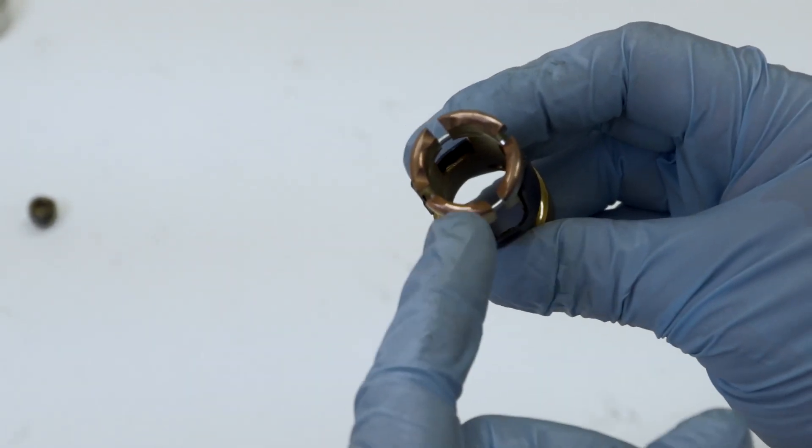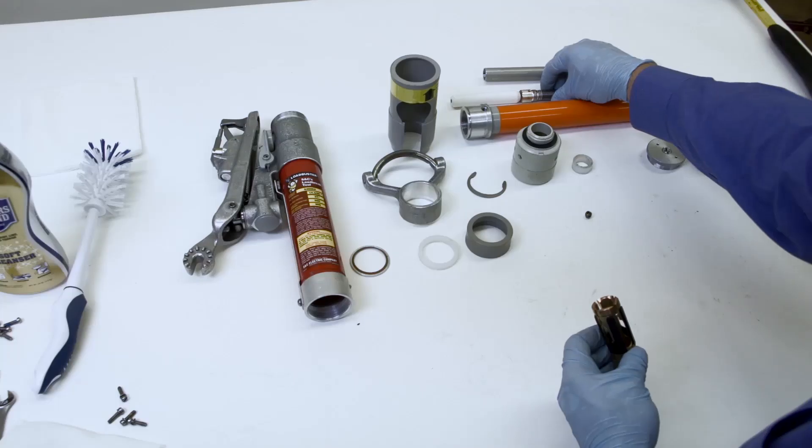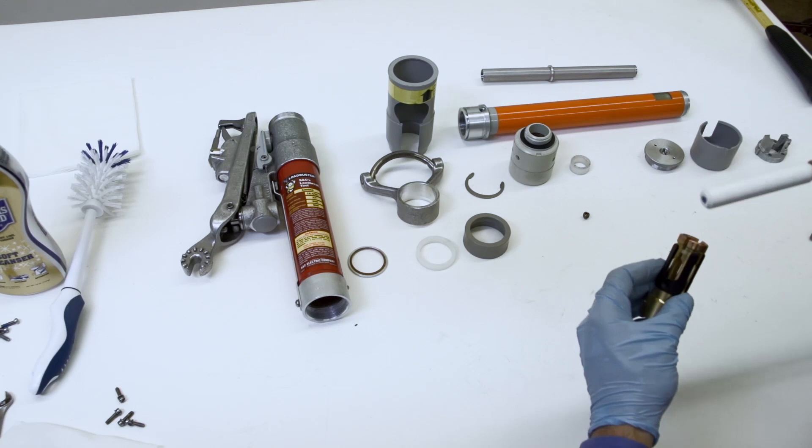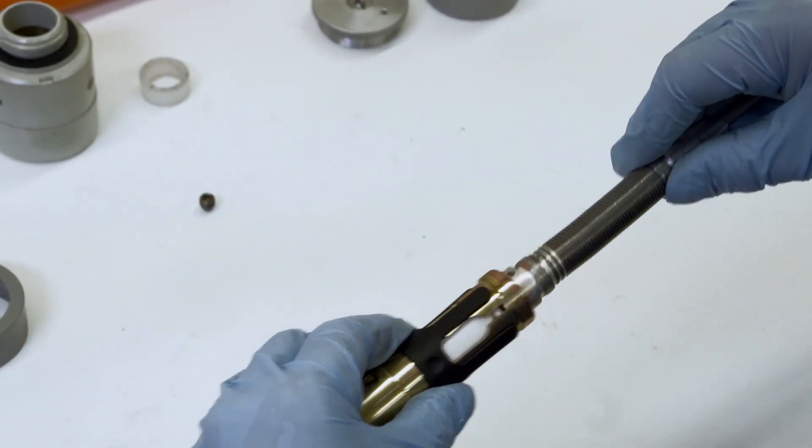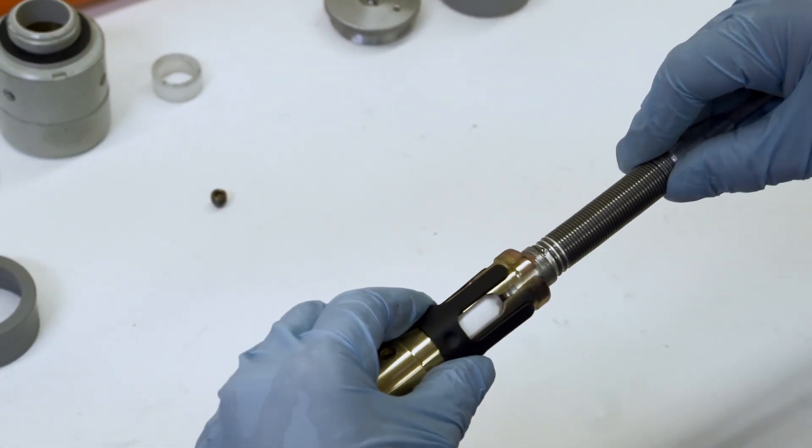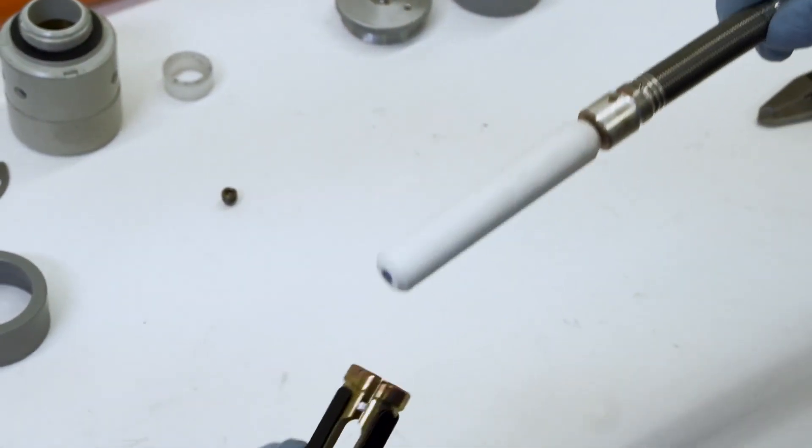Examine the steel ring inside the contact assembly. It should be round and the trailing end of the moving contact assembly should slide in the stationary contact easily. Replace the stationary contact assembly if it is bent.